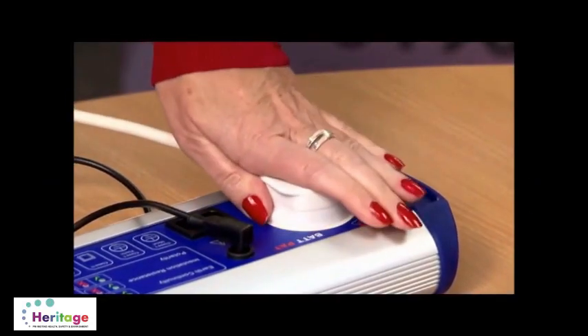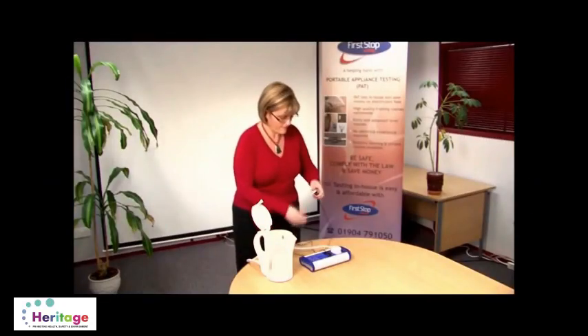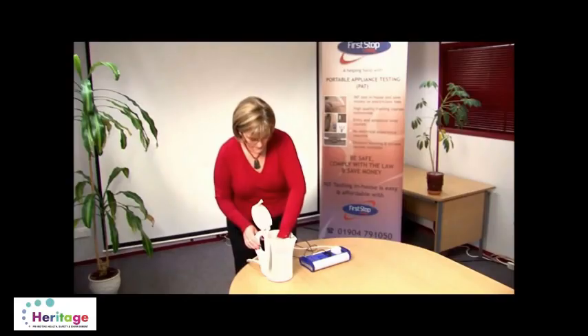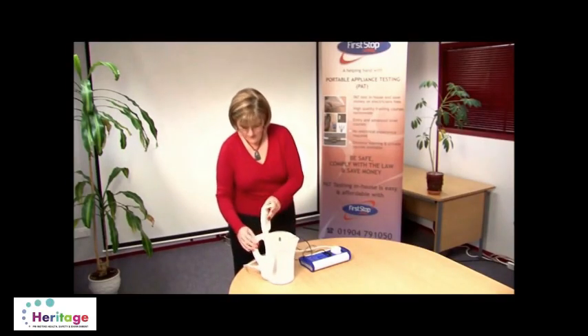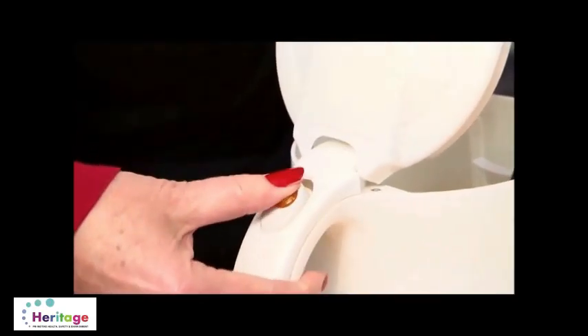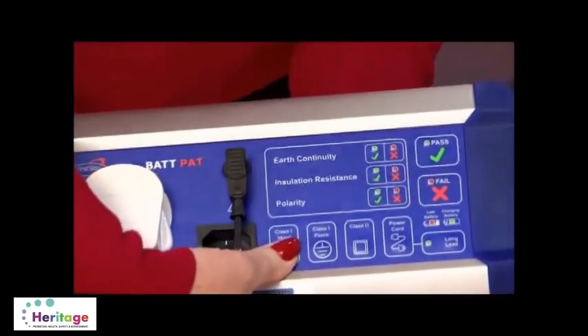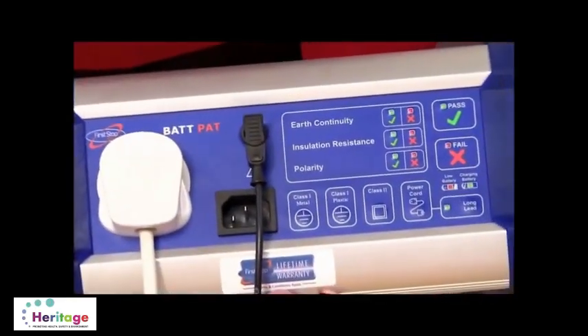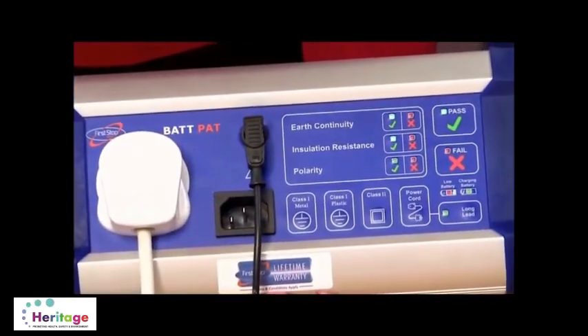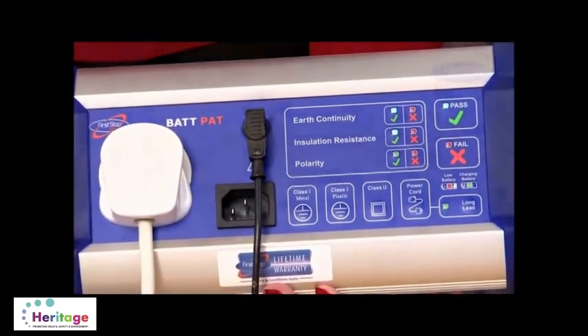Testing a Class 1 appliance. Plug the appliance into the BATT PAT and clip the test lead to a suitable earth point. Make sure that the appliance is switched on. Press the Class 1 button and wait for the BATT PAT to display the results of the earth continuity and insulation resistance tests.